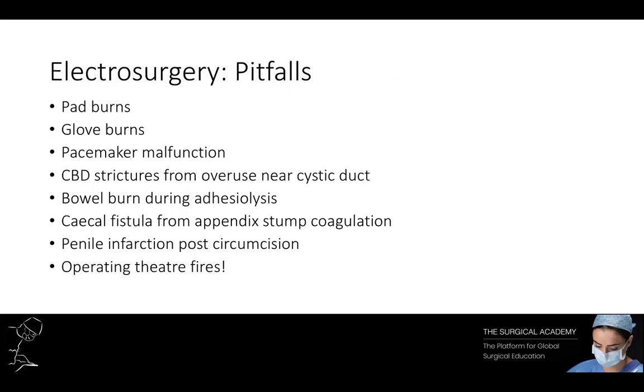We will now discuss common pitfalls when performing electrosurgery. The pad electrode is the second electrode in a monopolar circuit. Pad burns remain the largest group of complications from monopolar electrosurgery. It is as active in conducting current as the surgeon's electrode, but its large surface area prevents heating under the adhesive. The effective surface area of a pad can be reduced by changes in conductivity — for example, hair conducts poorly and can lift a pad, so the patient should be shaved prior to application. The edge of compression stockings should not cross the pad, as creasing changes pad conductivity creating hot spots and possible burns. High impedance tissues below the pad, such as scars and bony prominences, may also create hot spots and should be avoided. A pad should generally be placed over well-vascularised muscle bulk with the cable placed dependently to prevent peeling.